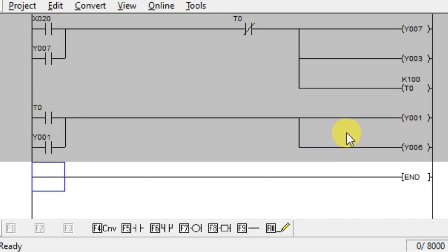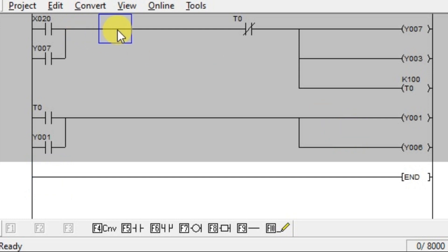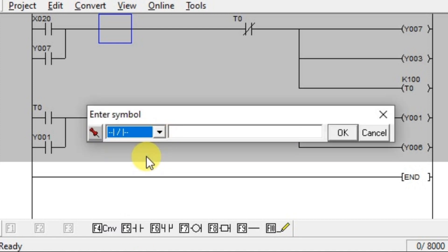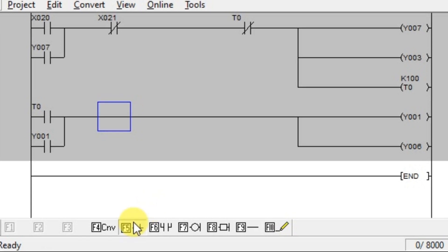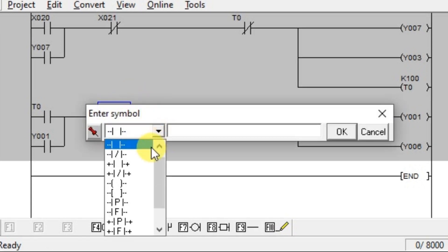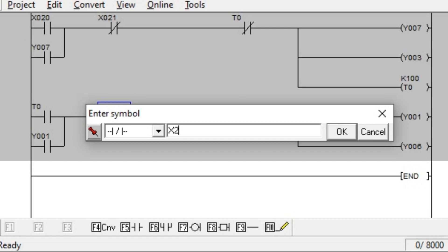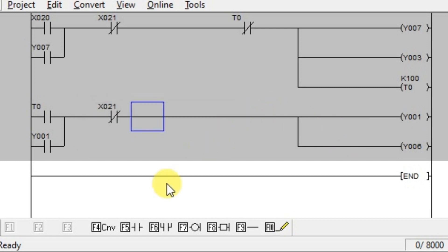Now we need to insert a reset push button. Whenever this push button is activated, all outputs must be turned off. We are using push button 2, address x21. We have to insert an NC contact of push button 2 so that whenever it is activated, it will turn off all outputs. Enter x21. Repeat the same in the second rung, add the NC contact with the same address x21, as the reset is common.